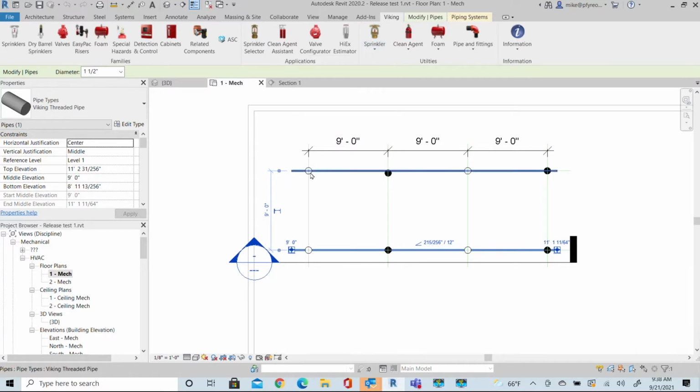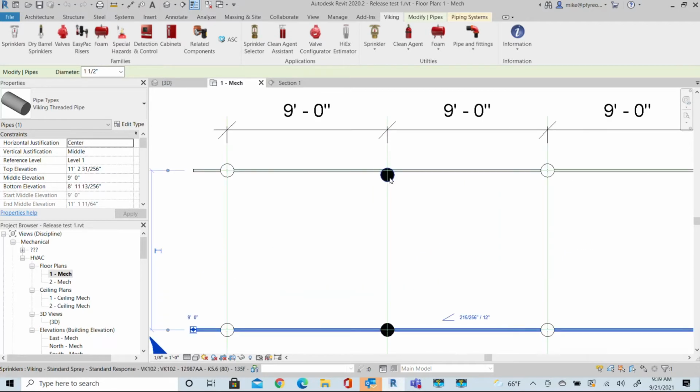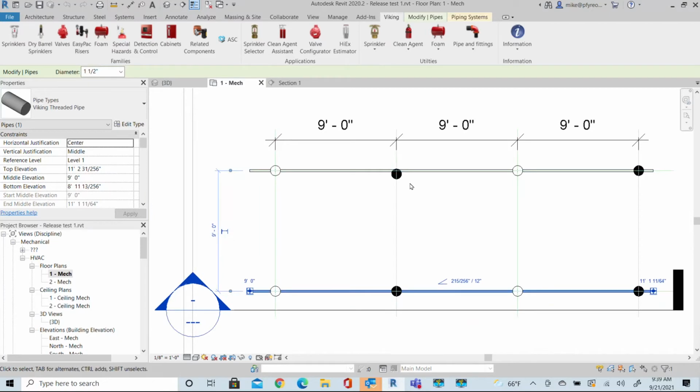What this does is take the sprinkler and connect it directly to the piping, directly to a fitting on the branch line or beam, so it's ignoring arm overs across this. In fact, in this case, you'll see we have one sprinkler head that's offset. What this will actually do is raise this sprinkler up to the pipe and line it up with the pipe. The pipe is the defining location for the elevation of the sprinkler.